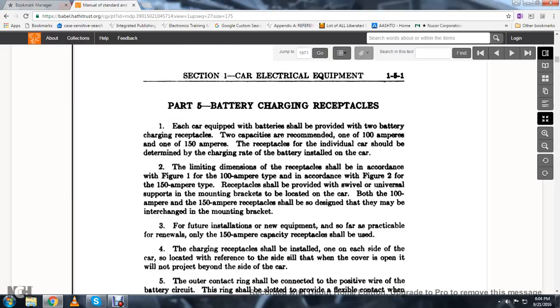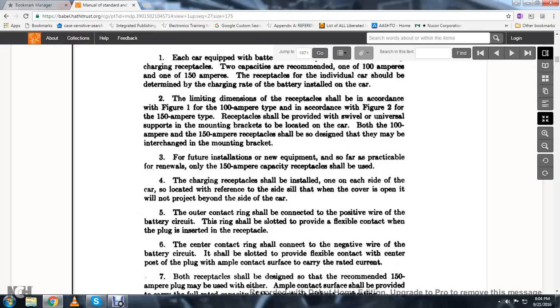Part Five, battery charging receptacles. Each car equipped with a battery shall be provided with a battery charging receptacle. Two capacities are recommended: one of 100 amperes and one of 150 amperes. The receptacle for individual cars should be determined by the charging rate of the battery installed. Limiting dimensions should be in accordance with figure one for the 100-ampere type and figure two for the 150-ampere type. Receptacles should be fitted with swivel and universal supports for mounting brackets located on the car.